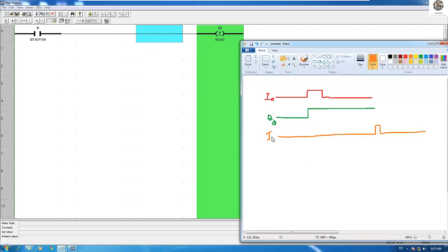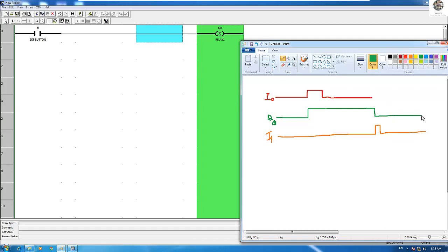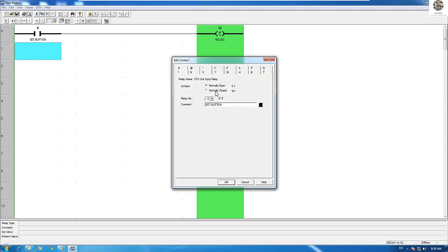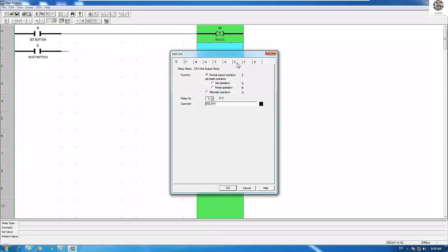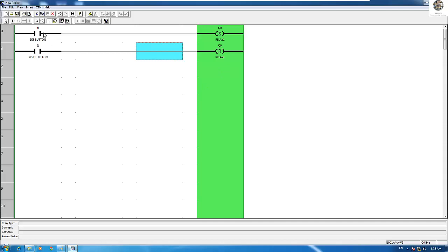So when I turn on I1, the Q0 will be off. Let's add the I1 for resetting Q0 — I1 is the reset button, and it resets Q0. So when I push I0, Q0 will turn on, and when I push I1, Q0 will turn off.